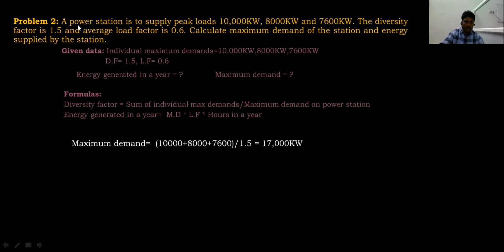In the next line, what is asked is the energy supplied by the station. The energy supplied by the station is equal to the maximum demand, which we have already derived from the previous formula, into the load factor already given in the data, and the hours in a year. The hours in a year are 8760, as we know from the previous problem.